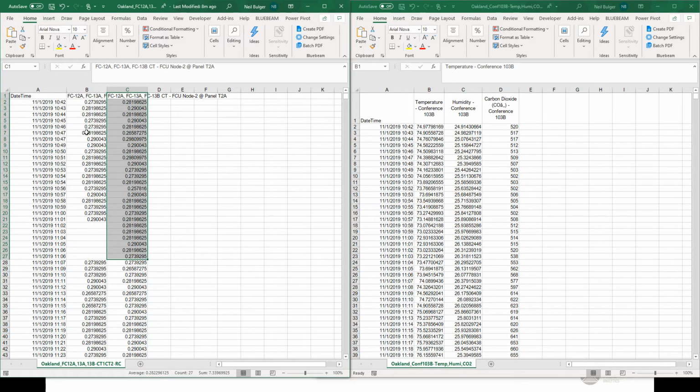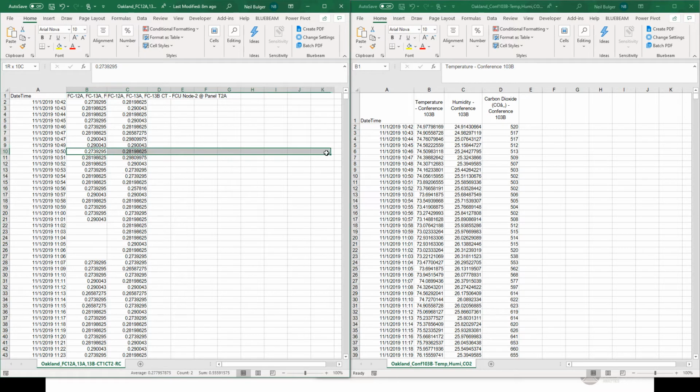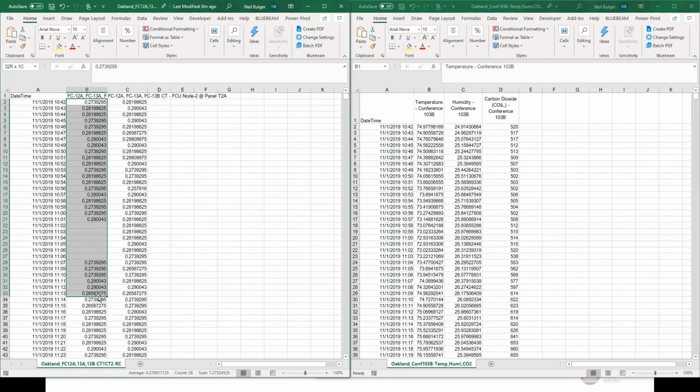And so what we're asking is basically now to plot temperature versus power. And these two CSV files, while they do have time as their common denominator, it is not as easy as you would think to establish a whole matrix of data. We're basically now making a large matrix where we can ask questions across the data. Generally speaking, most building end-use metering systems will just keep one data set with its own timestamp and will not quickly be able to compare a data stamp to another data stamp independent of time.